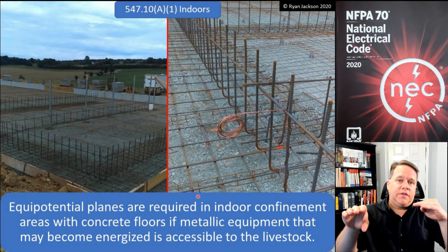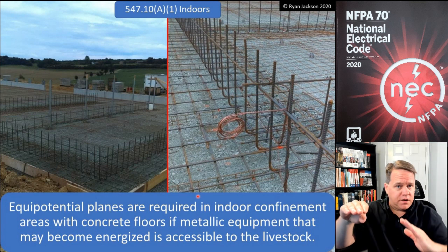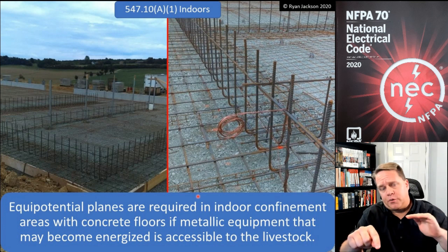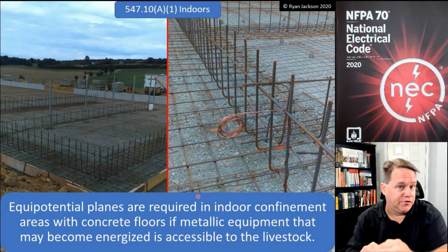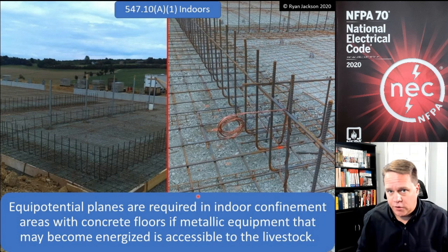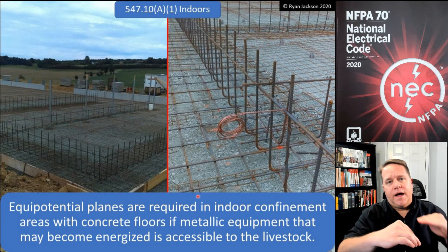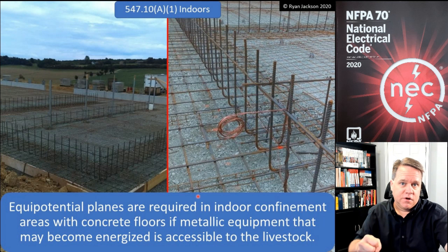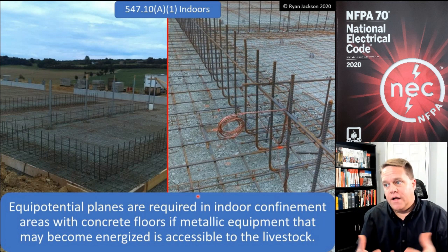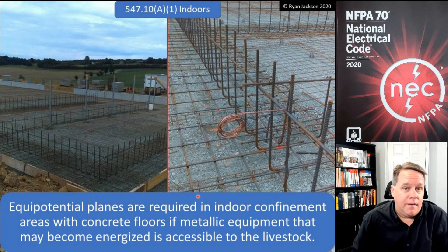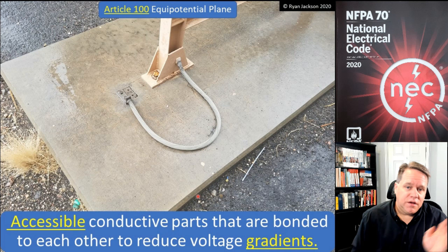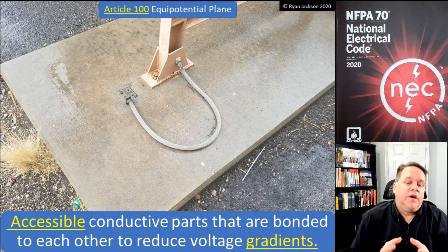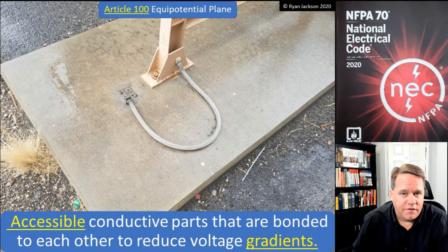If you keep one test lead on the concrete and move the other out into the dirt where the cows enter the barn, as you move your test leads farther apart, the voltage gradually increases toward three volts. By burying the rebar down at an angle from the slab edge, as the cows approach the floor the voltage difference diminishes — about half a volt with every step. A cow can handle half a volt; what they can't handle is three or five volts. That gradual plane ensures the difference between their front and back hooves is never dramatic enough to cause harm.